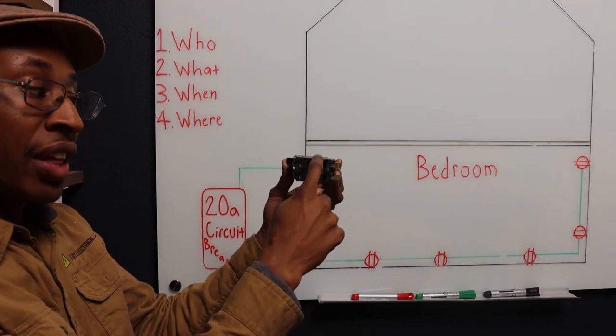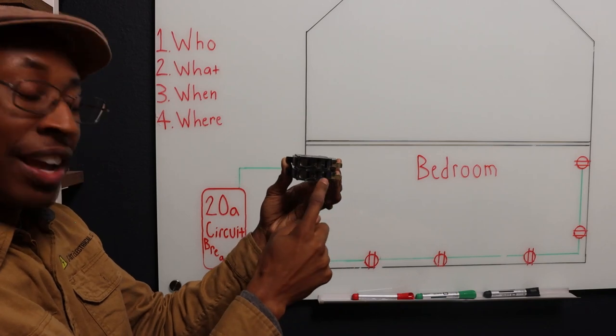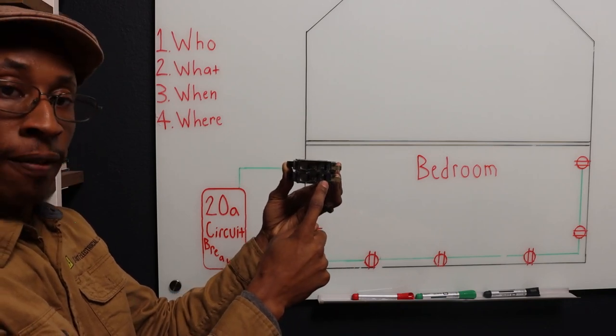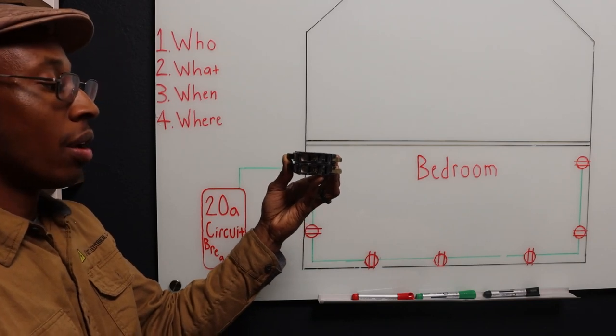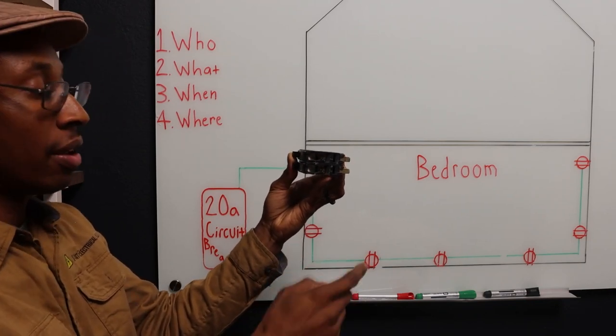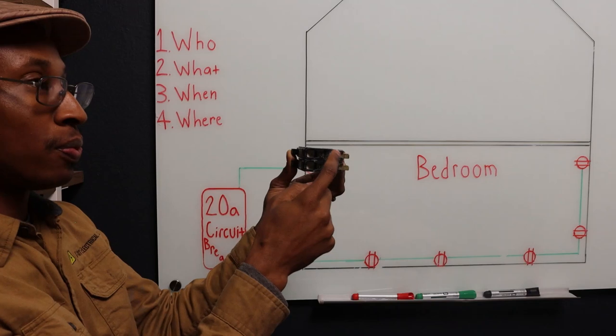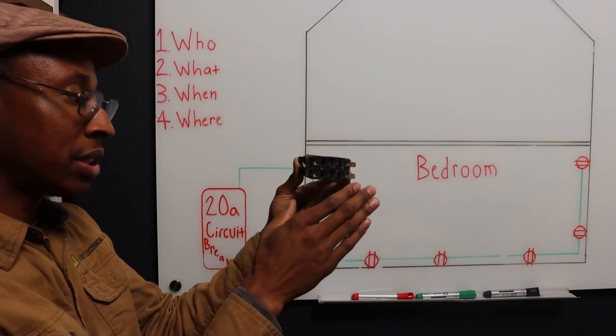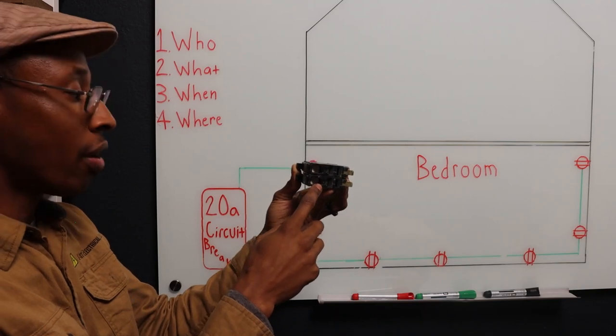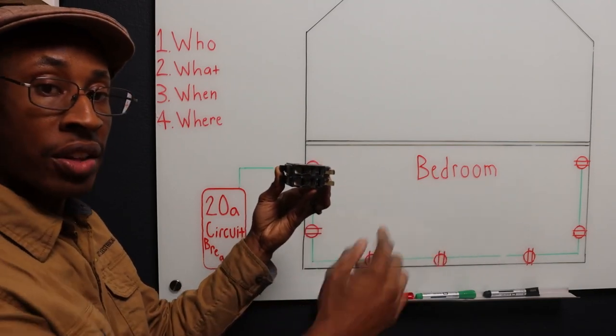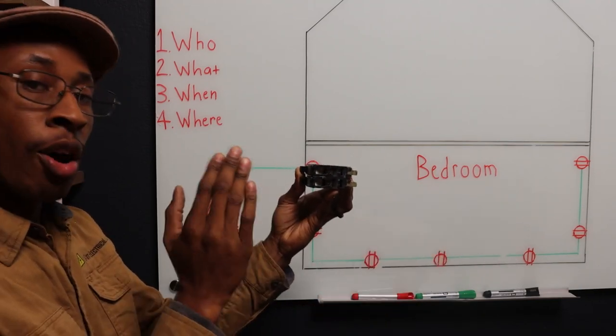The wire that you took off of this breaker, put it in the known good breaker here. So what we just established: we're going to establish if the breaker is the issue or if it's the issue down the line. Now go back and turn your power back on.